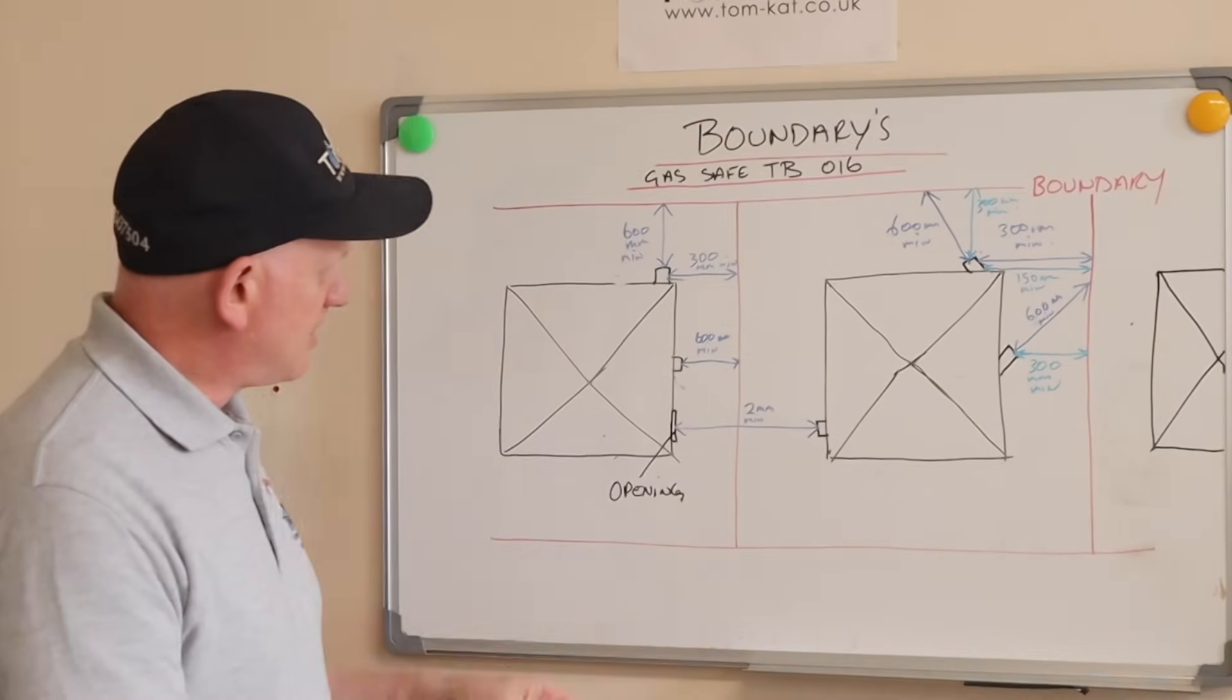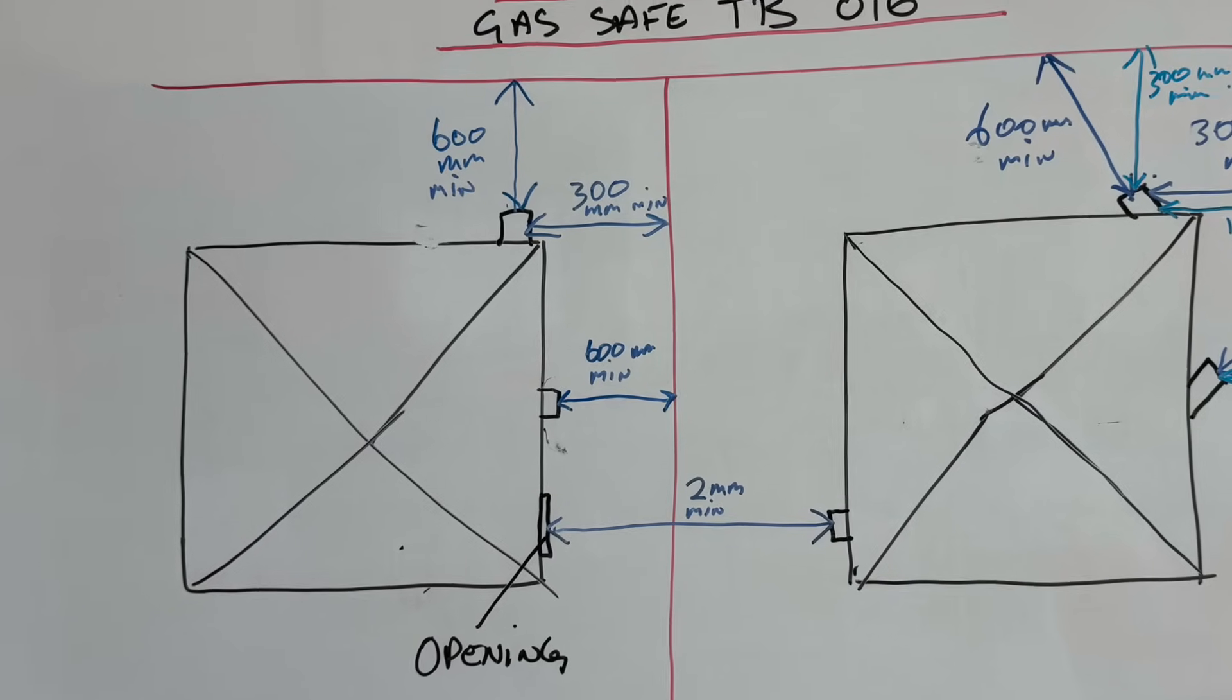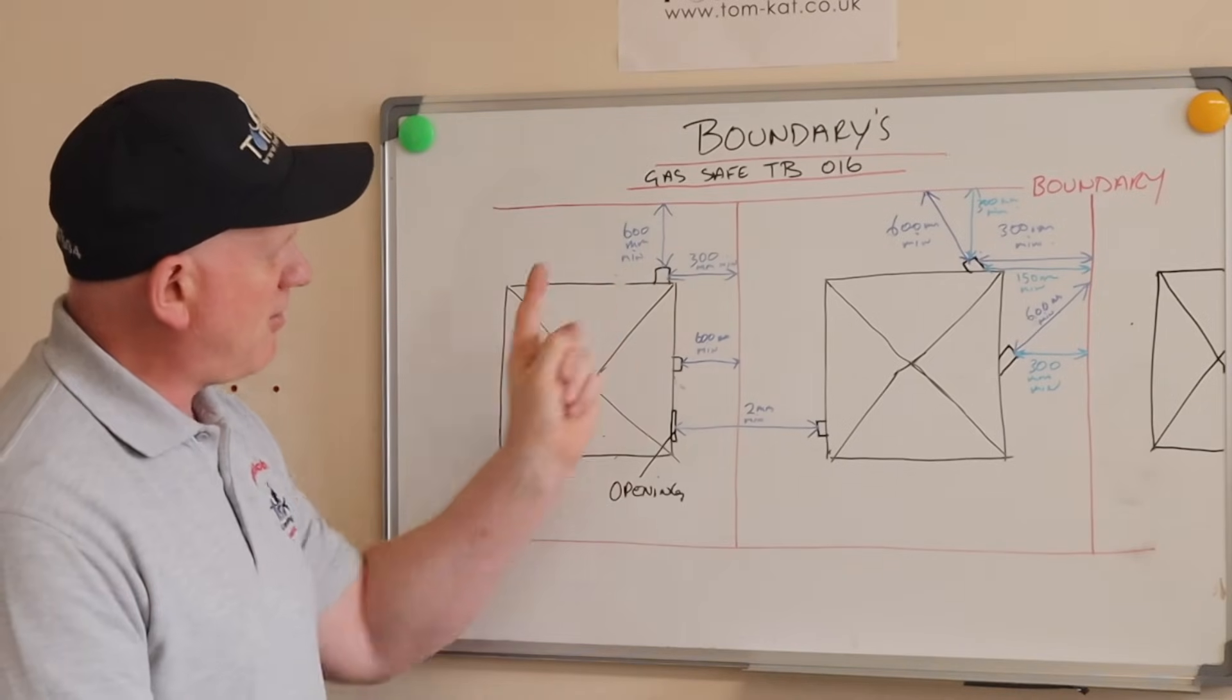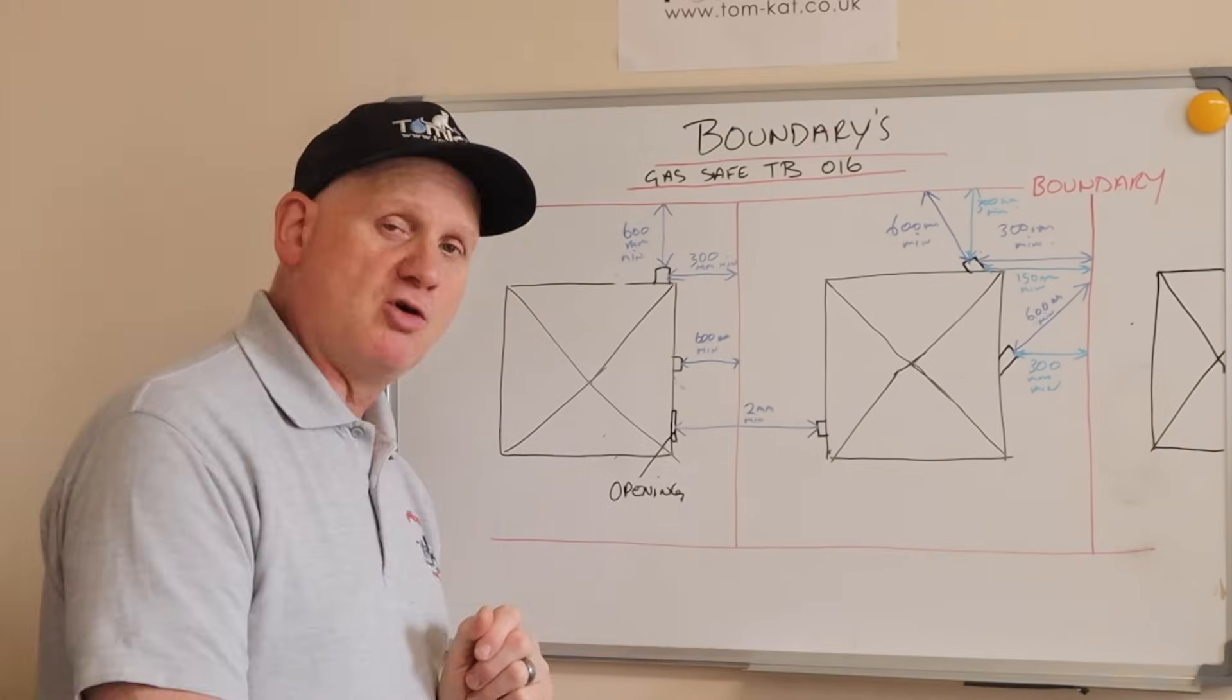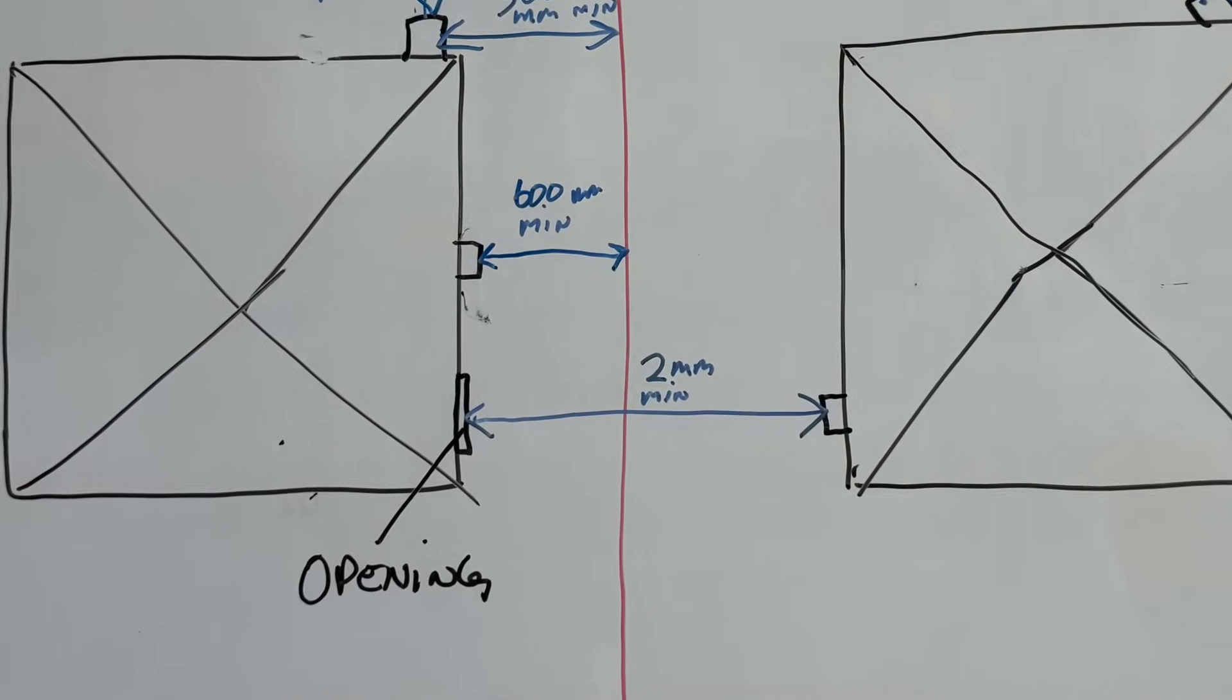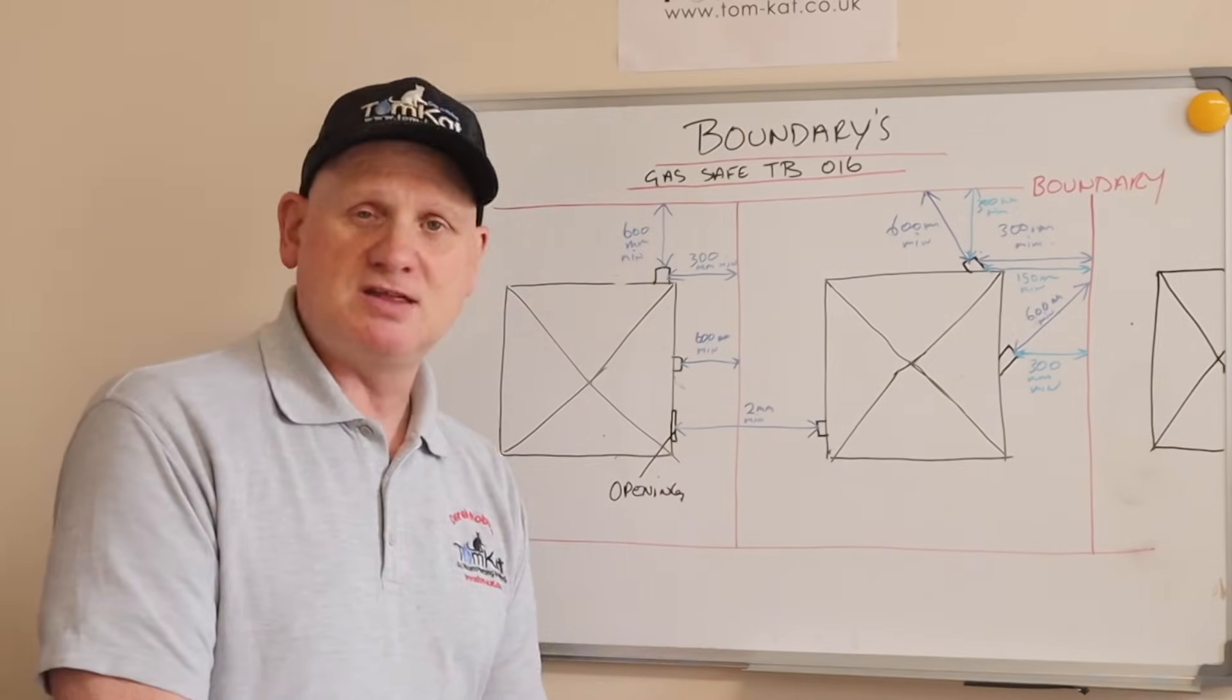Now, according to the building regs, if the flue is facing a boundary, we need a minimum of 600mm. If the flue is parallel to the boundary, from the side to the boundary, we need a minimum of 300mm. And if we are directly across from an opening into the building, window, door, then we need a minimum of 2 metres.